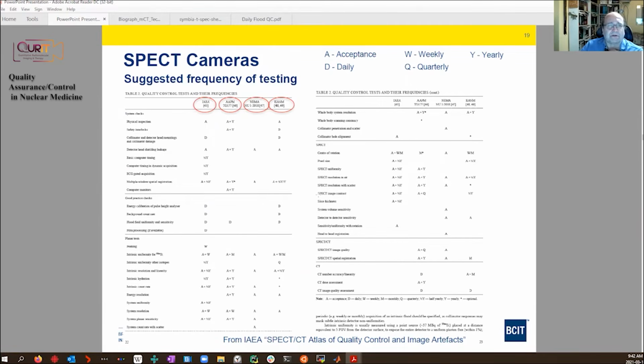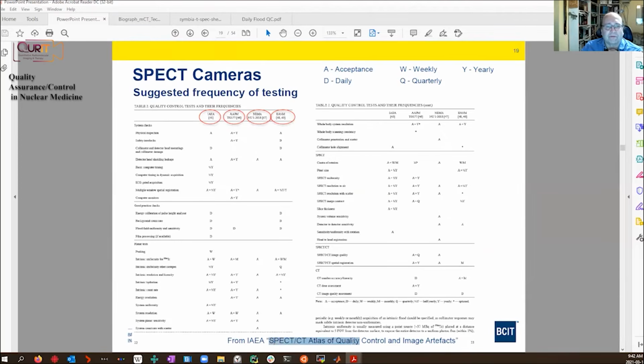Now, as I said, there are a number of recommendations for this. This is from the SPECT Quality Control Atlas. These are four different recommendations: from the IAEA, from the American Association of Physicists in Medicine, from NEMA, and from the European Association of Nuclear Medicine. It lists their recommendations for tests to be done during acceptance testing and daily. So down here, for example, we see that most of the organizations recommend flood field uniformity and sensitivity to be tested daily.